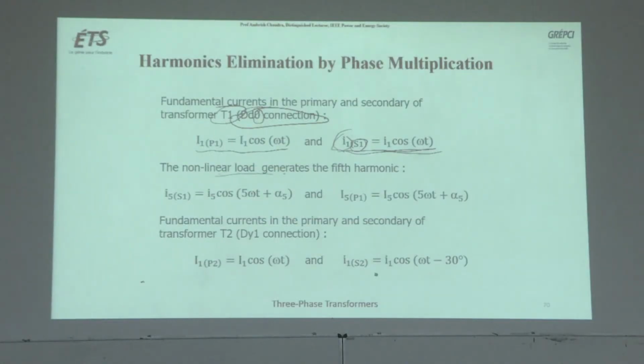Now, suppose your nonlinear load is generating 5th harmonic on the secondary side, and this is the equation for the 5th harmonic, which you transfer to the primary side. This is DD0, so there is no phase shifting in the current. They are in the same phase, 5th harmonic, right?